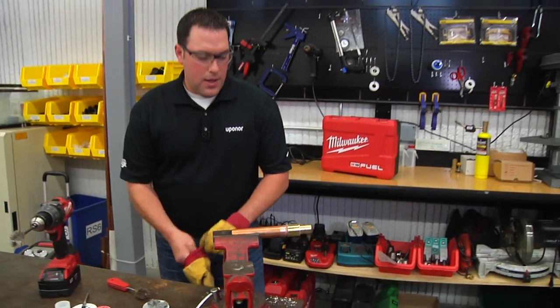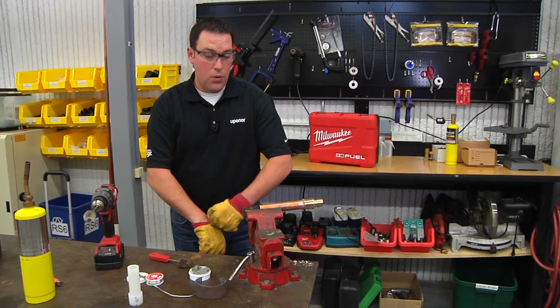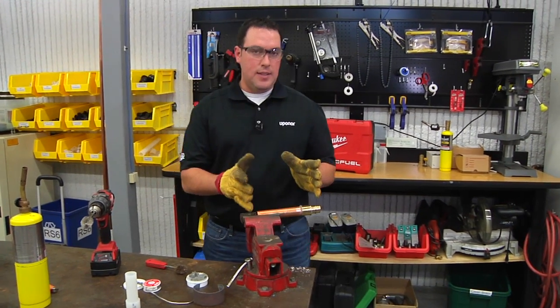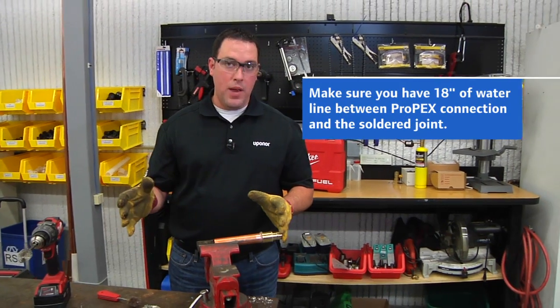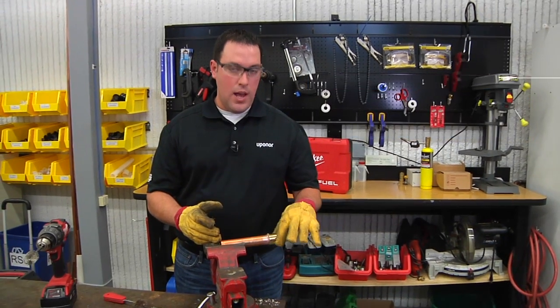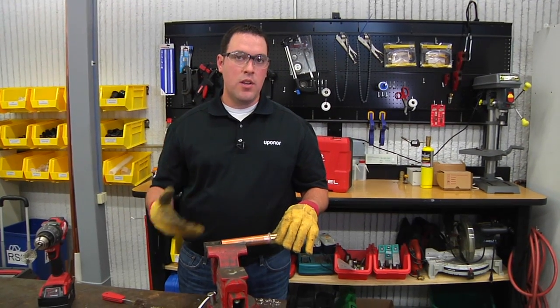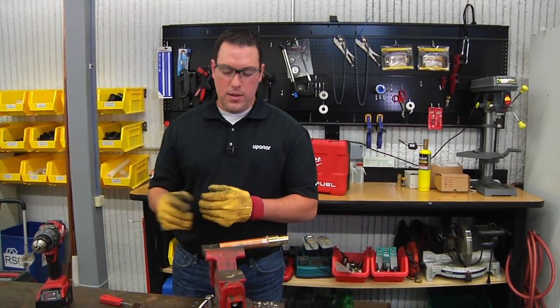We can then begin to solder the connection. Uponor recommends you have at least 18 inches of water line between the Propex connection and the solder joint. Best practice is to solder the connections before making a Propex connection so that the heat doesn't transfer to the PEX.